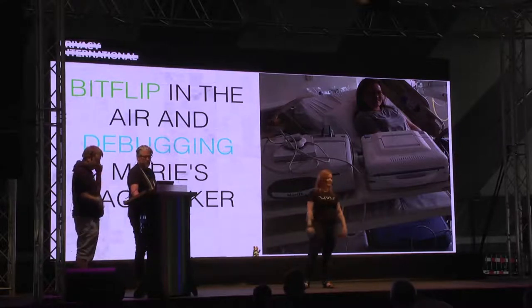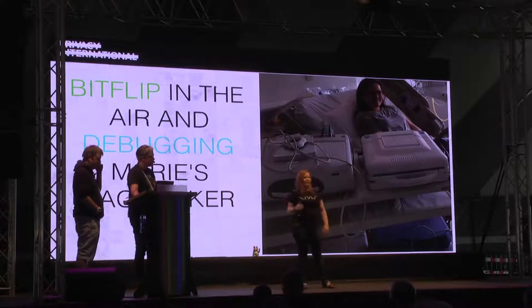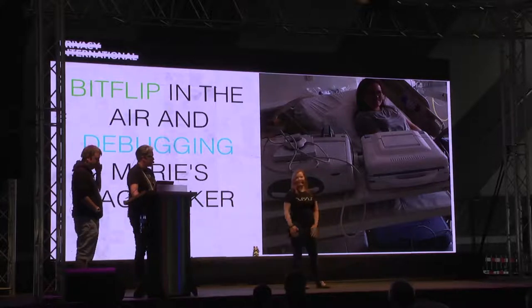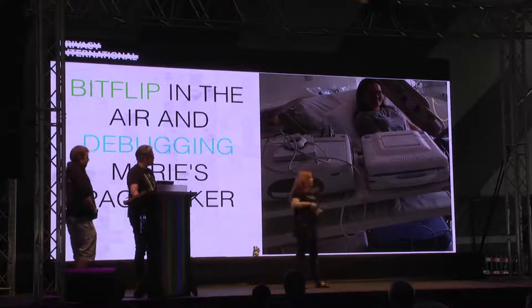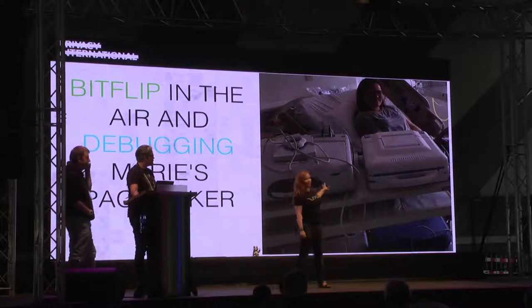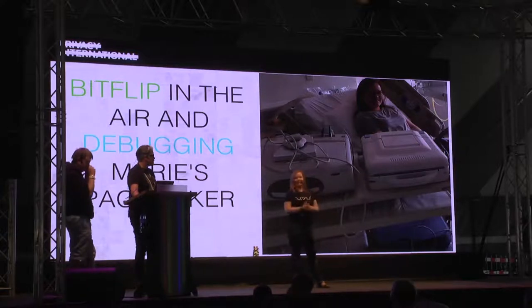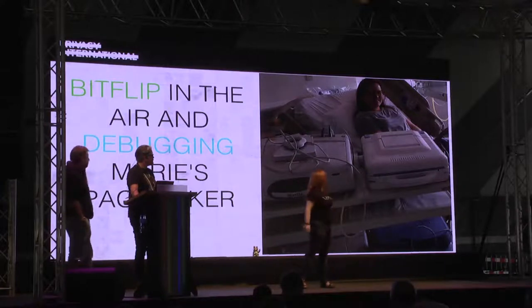I notified the air crew. When we landed at Schiphol, there was an ambulance waiting for me that took me directly to the hospital. I had to spend the night there because I didn't have a pacemaker technician in at the time. This is me the morning after, when they're rolling in the table with the pacemaker programmers - you can see four different brands of programmers. They have to use the programmer that is actually from the same manufacturer as my device, because all the wireless communication protocols are proprietary, so there's no open standard for this. You have to match the correct programmer to the correct device.